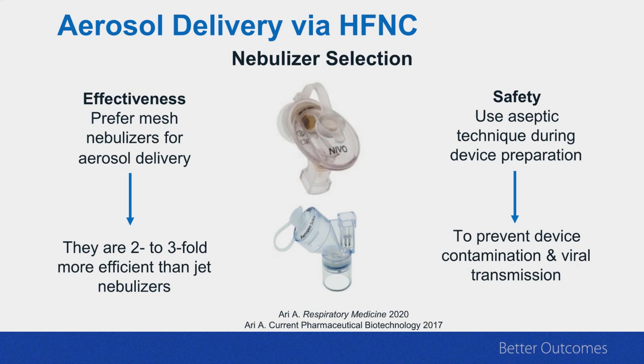Because when you use the jet nebulizer, it adds additional flow to the system, and that's something we don't want to do. You need to adjust the flow rates. So when you use a nebulizer with the high flow nasal cannula, make sure that you use an aseptic technique during device preparation to prevent device contamination and viral transmission. Place the mesh nebulizer prior to the humidifier. Previous research showed that when you place the mesh nebulizer prior to the humidifier, you increase the delivery efficiency of the device compared to its placement near the patient.